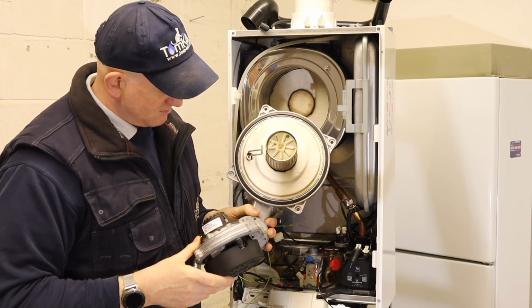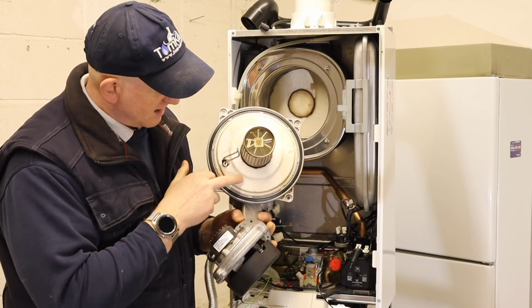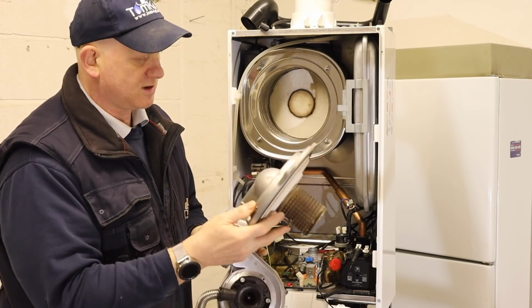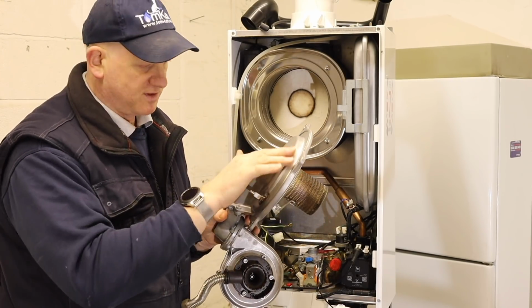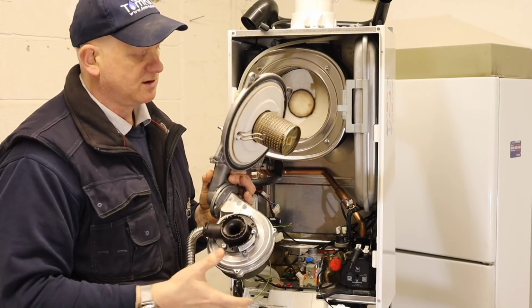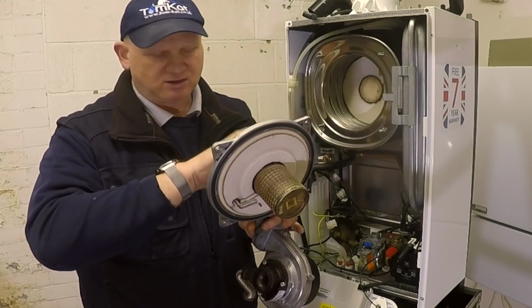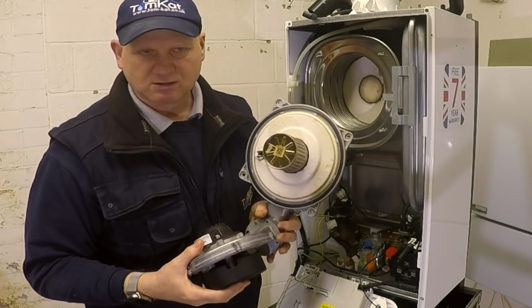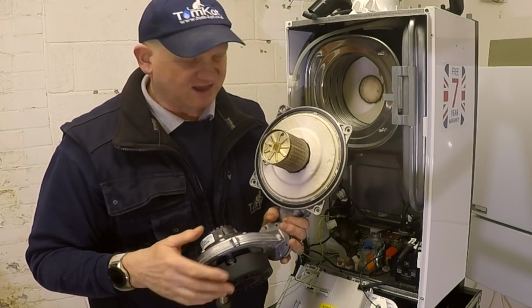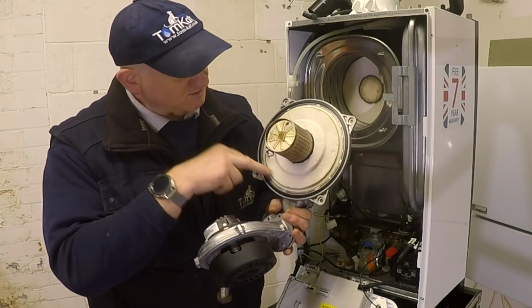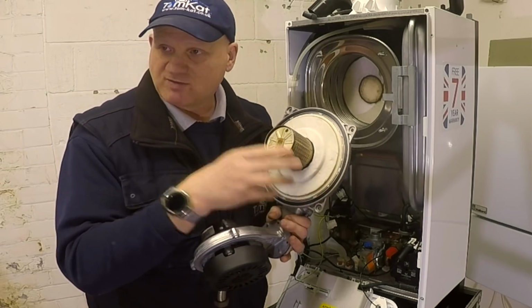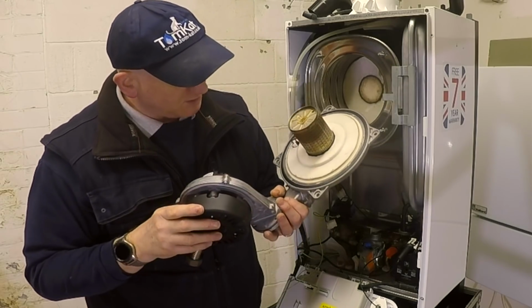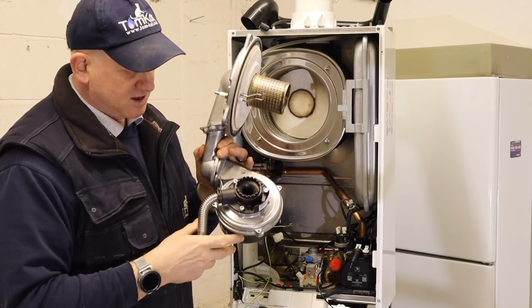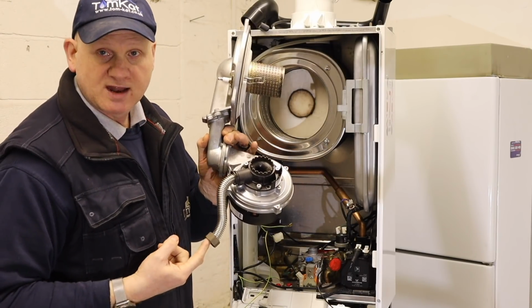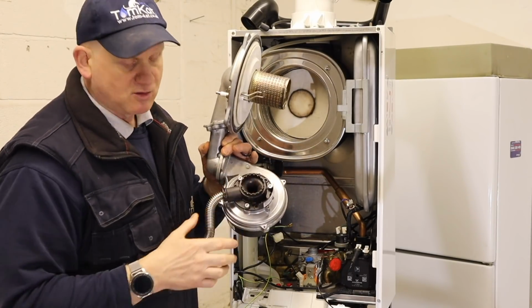360 degrees around. We've also got our heat shield here, because this is to stop this becoming hot. So they say it's a cold touch. Not that cold. It don't cool it that much, but there you go. And so we've got to make sure that this isn't damaged, and if this is damaged, then it will need to be replaced. And now you can see where the gas comes in here and the air goes in there.